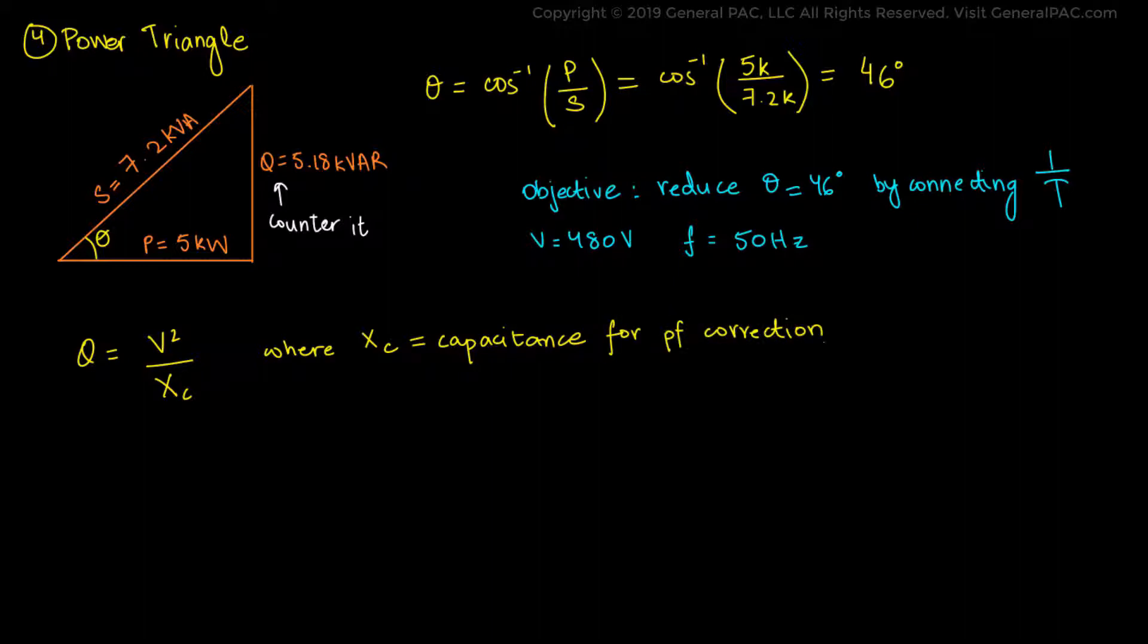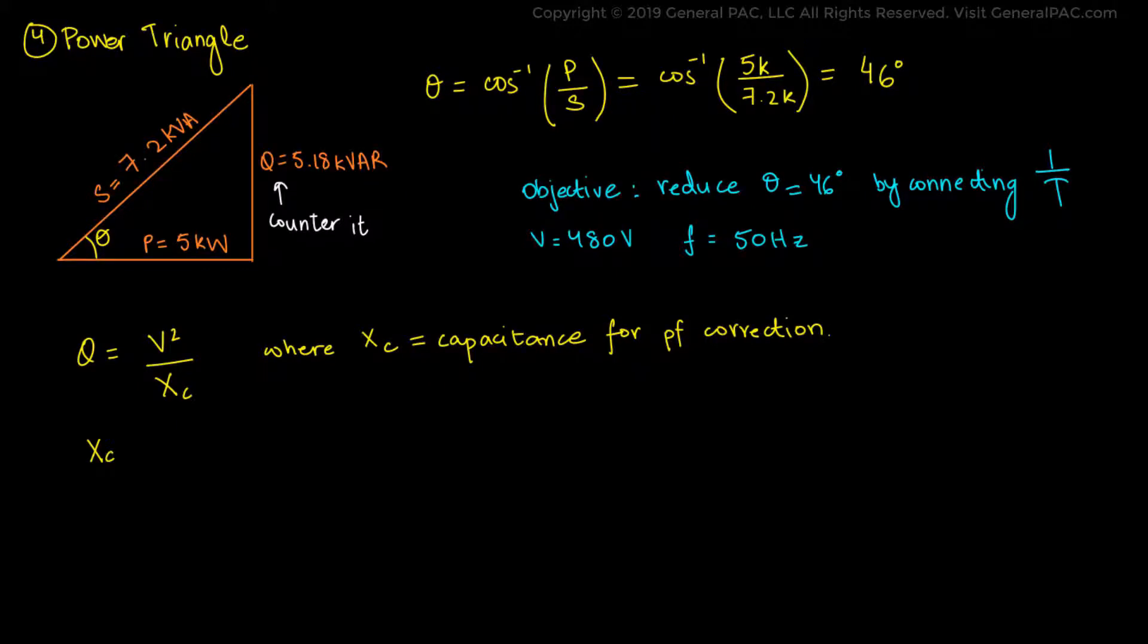Rearranging the equation, Xc equals V squared over reactive power, which equals 480 squared divided by 5.18 kVAR. Plugging in the values and solving, we get 44.478 ohms.